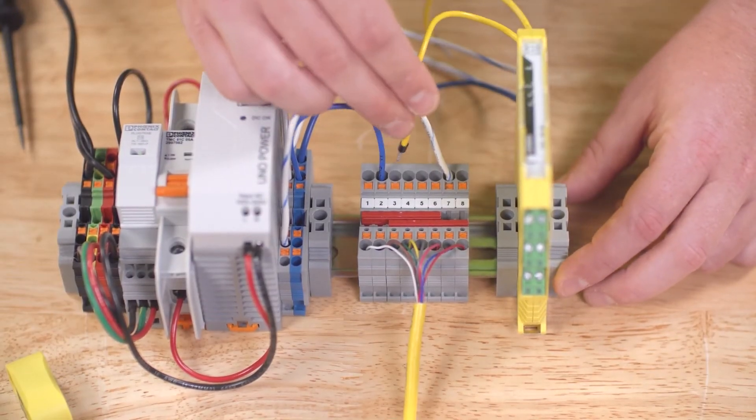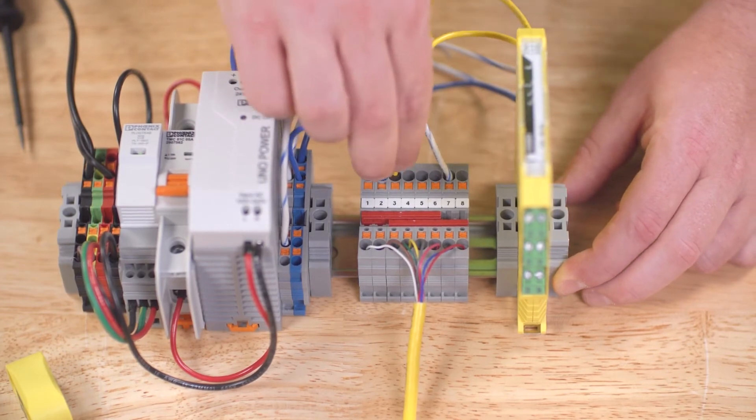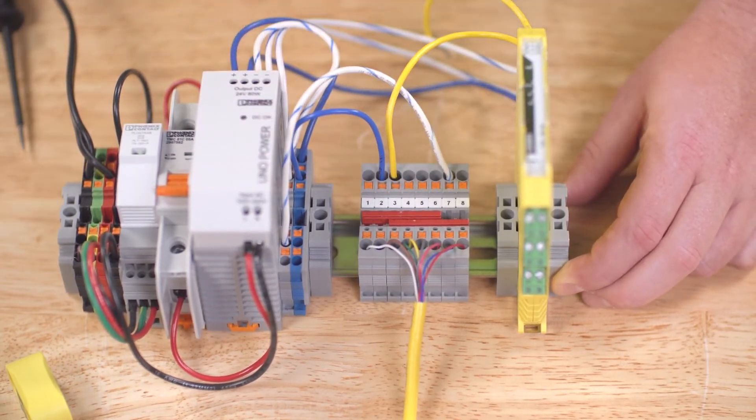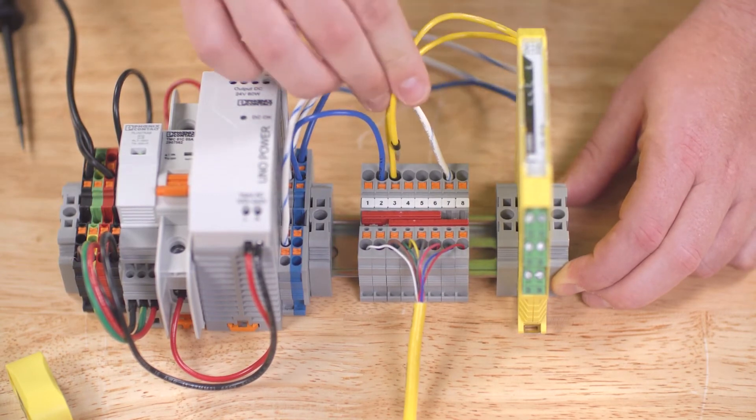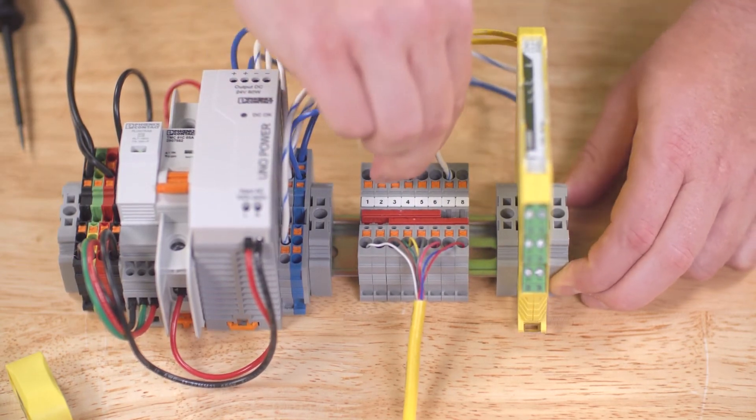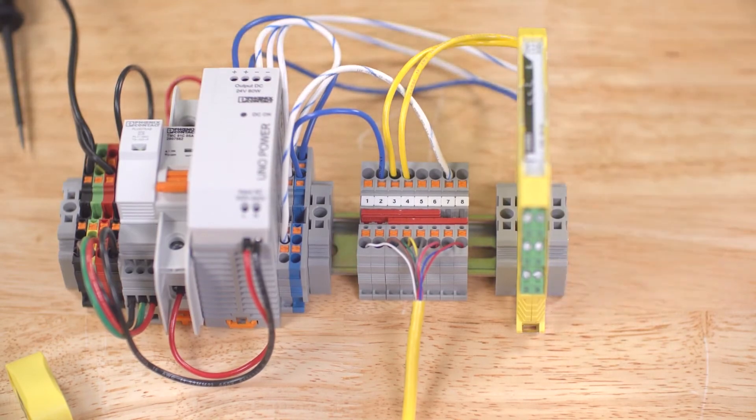Finally, we'll connect the safety outputs F-O-1A and F-O-1B to the safety relay sensor channels. Pin 3 connects to S12 and pin 4 connects to S22 of our PSR MC40 relay.